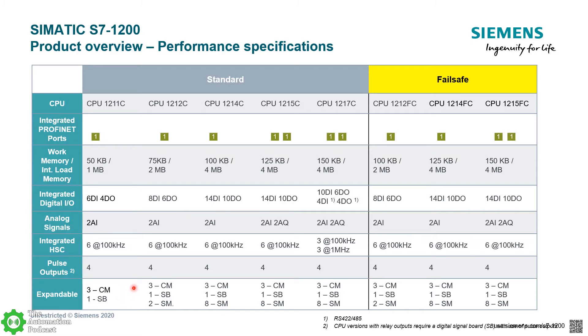The expansion capabilities also change between models. With the 1211, you're limited to the integrated IO plus communication expansion — up to three communication modules to the left. With the 1212, you get up to two signal modules plus the three communication modules and the signal board. With the 1214 and up, you can expand up to eight local IO modules, and all models support distributed IO up to 16 PROFINET IO devices.